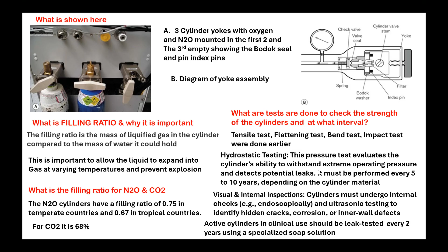And also we are using ultrasound and visual and internal inspection, and active cylinders should be tested for leaks using a specialized soap solution also. And ultrasonic testing is also done to find out hidden cracks or corrosion in all the vessels. So these four tests were the earlier tests done: tensile, flattening, bend test, and impact. But the modern testing is hydrostatic testing, visual and internal inspection, including ultrasonic testing, and active cylinder testing using specialized soap solution.